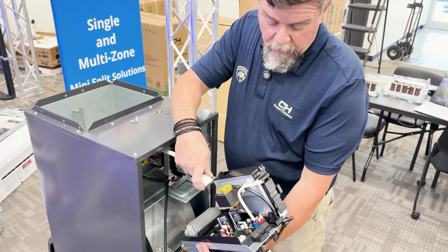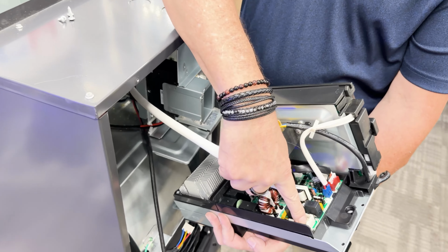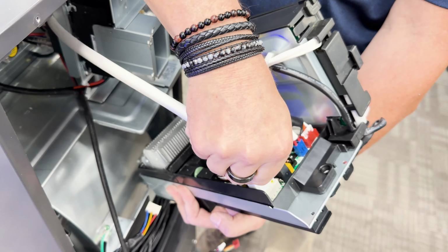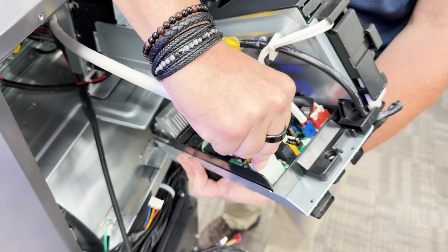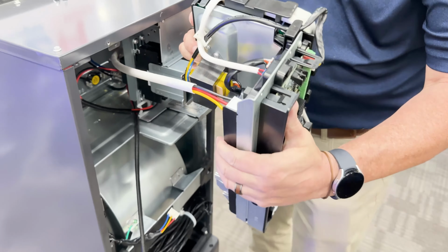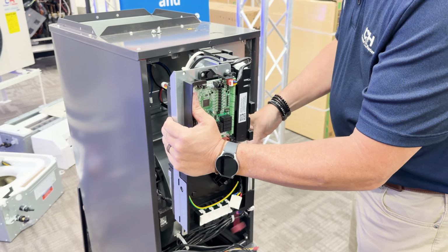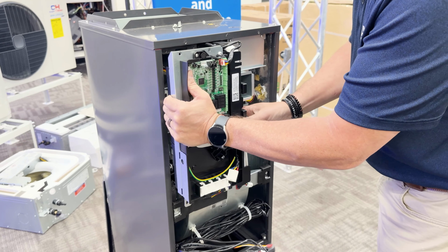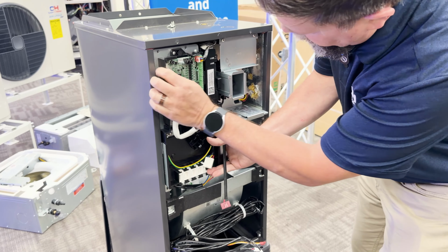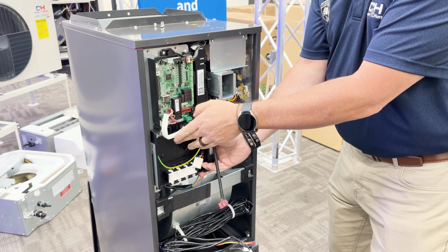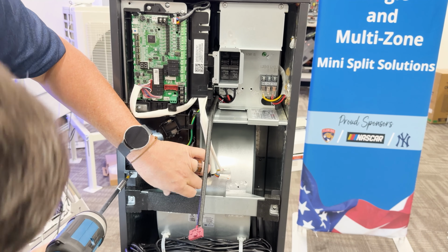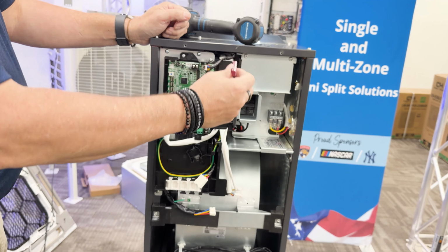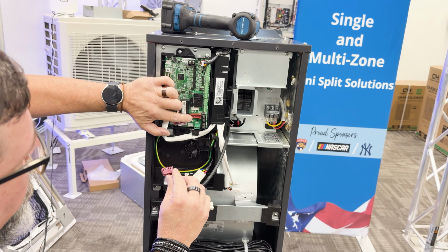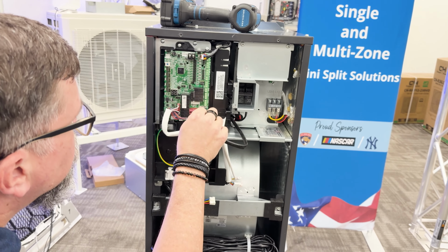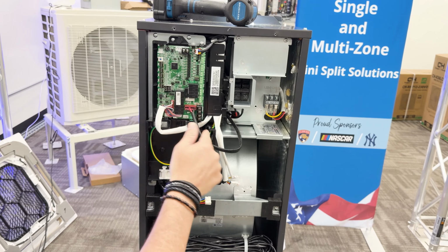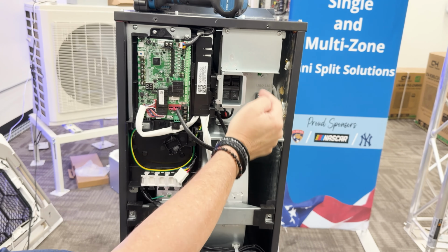So before putting the circuit board assembly back in, you'll see where we disconnected the plug before. We're going to plug this in right here. Make sure it's good and snug. And then we can slide the assembly right back into place. And we'll have the 1, 2, 3 screws here. And we'll take the control voltage and we'll plug that right here into CN14. And this is what provides 24 volts to the relay that activates the heater kit.